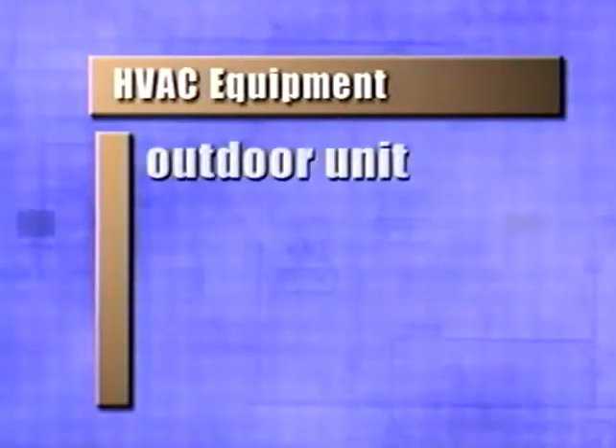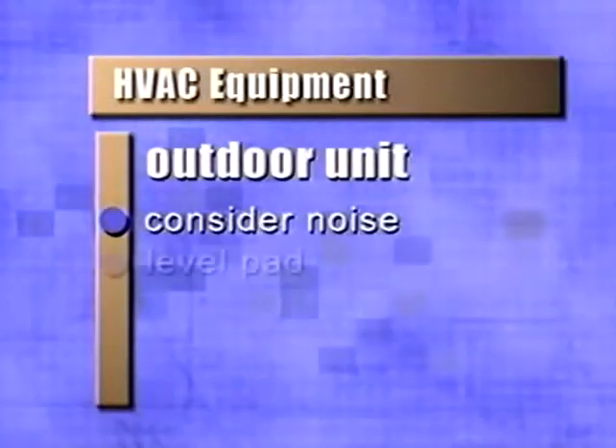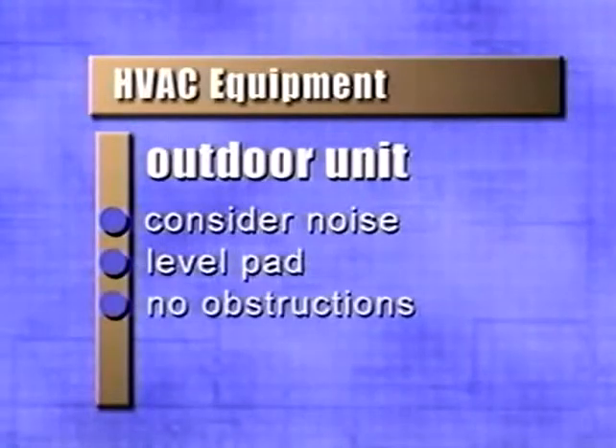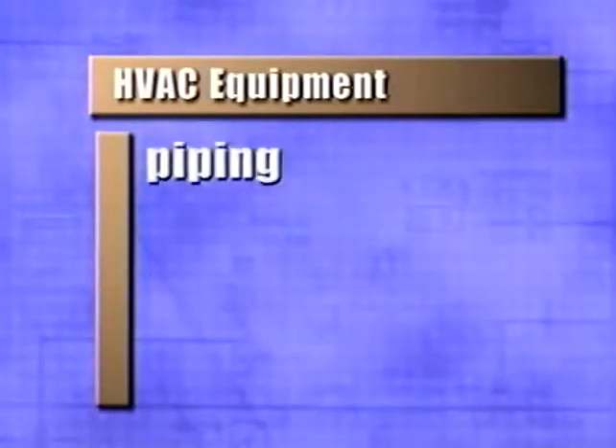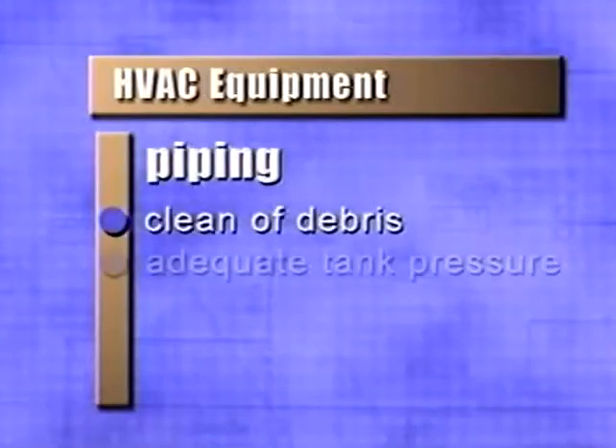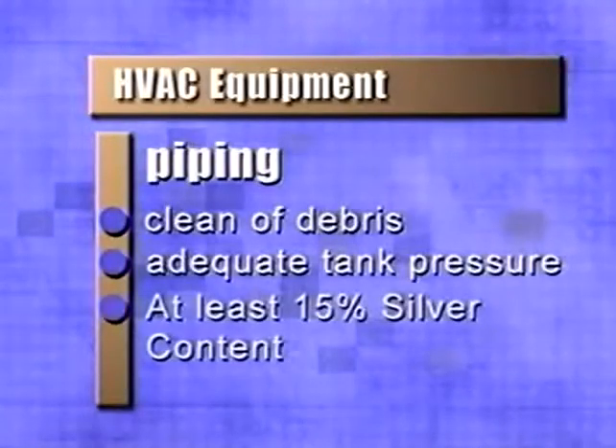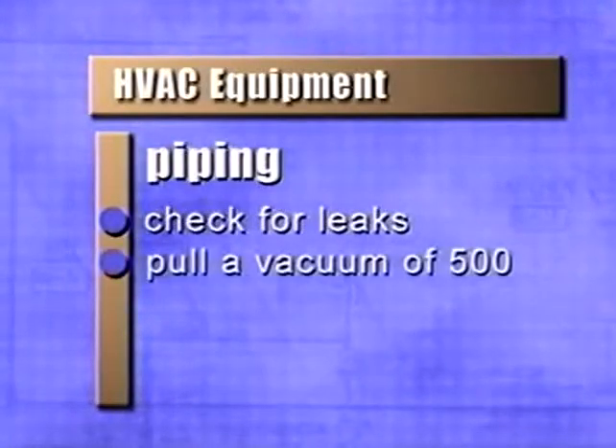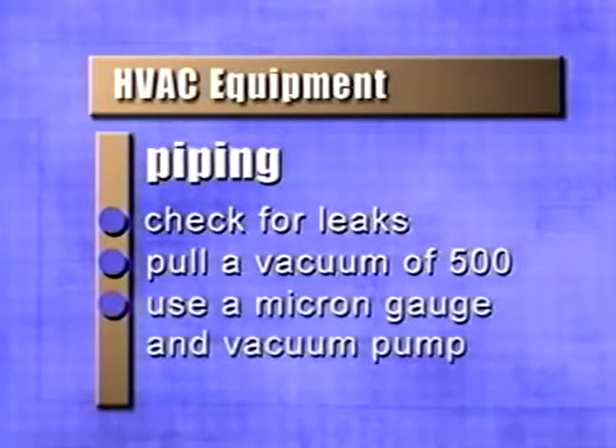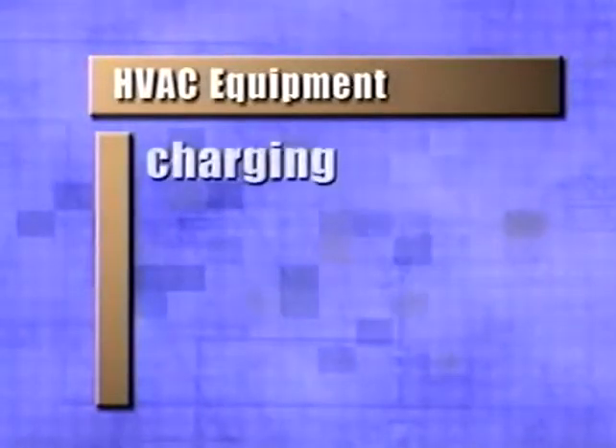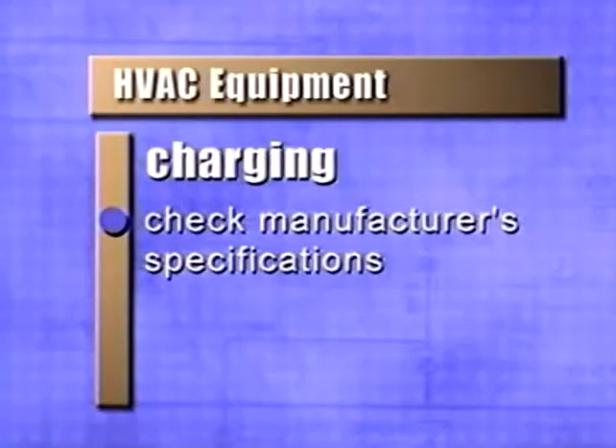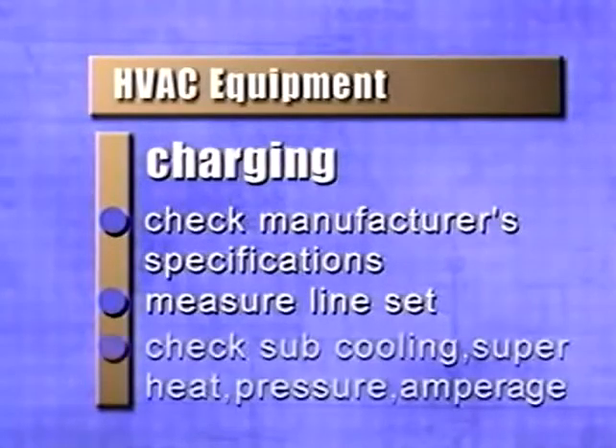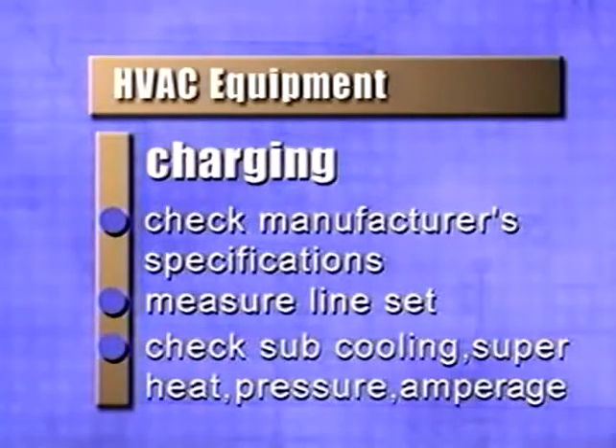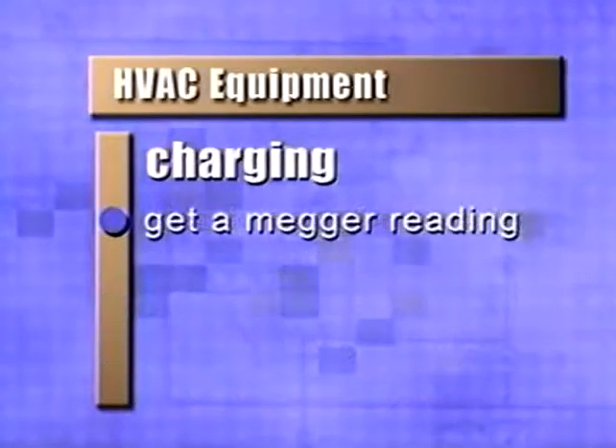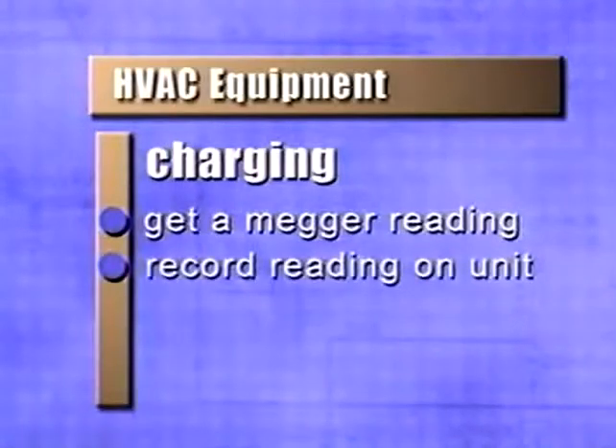When setting outdoor units, place where noise won't be a problem. Make sure the pad is level and there are no obstructions. When installing refrigerant lines, make sure the line is clean of debris, the tank pressure is adequate, and the solder has at least 15% silver content. Check for leaks in the line by pulling a vacuum of at least 500 using a micron gauge and vacuum pump. When charging the unit, be sure to check the manufacturer's specifications and measure the line set. Check the subcooling or superheat temperature, pressure, and amperage. Finally, get a megger reading and leave it for future service technicians.